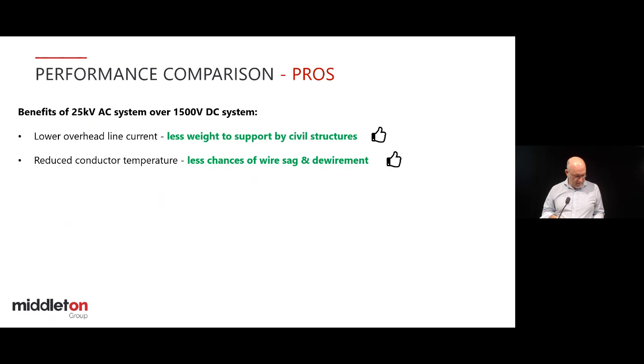That's a good thing. Another good thing about AC systems is that electrolysis is limited. AC electrolysis is known, but its effects are very much less, less than 5% of what they are for a DC system. Just a reminder that driven electrolysis via the stray currents that escape from the return rail system can drive corrosion rates of up to 9.2 kilograms per amp per year. So you can imagine if you've got a few hundred amps flowing through the return path through third party or rail assets, you can get a lot of steel disappearing very quickly into nothing. So that's another positive.